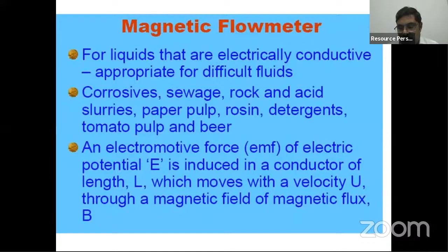So this is very simple. See here, the pipeline is enclosed with a permanent magnet, or it may be an electromagnet. When the flow takes place, because of the movement of the fluid within the magnetic field, an EMF will be induced. By measuring the induced EMF, you can measure the flow. So basically E is equal to U bar B L, where U bar is the velocity, B is the magnetic flux, and L is the diameter of the tube. Here B and L are constant, so the induced EMF will be directly proportional to the velocity.